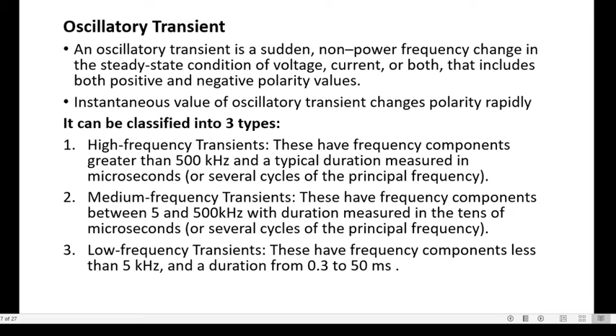It can again be classified into three different types: high frequency transient, medium frequency transient, and low frequency transient. A high frequency transient has a frequency component greater than 500 kilohertz. Obviously, that is non-power frequency, far greater than 50 Hz, and a typical duration measured is in microseconds. Medium frequency transients are between 5 and 500 kilohertz. And low frequency transients have a frequency component less than 5 kilohertz.